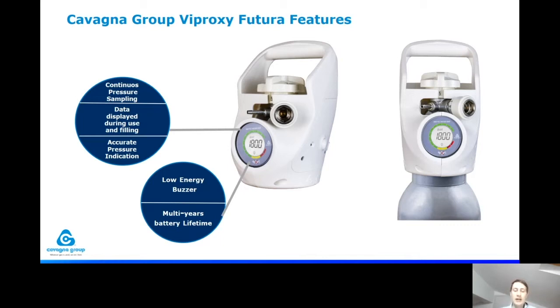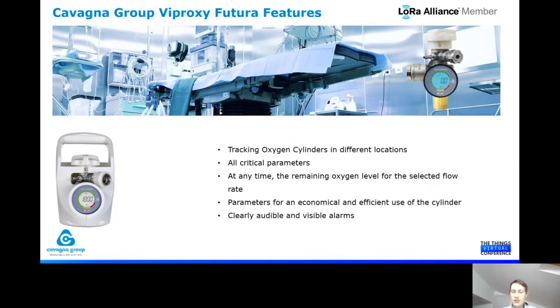This device, adding the LoRaWAN capabilities and communication, allows tracking of the oxygen cylinder in different locations, which is very important because this asset is crucial for the healthcare sector. We can monitor all the data the device collects, related to critical parameters of the patient, improving the service that nurses or doctors can offer. At any time, we can see the remaining oxygen level according to the selected flow, allowing a better and more efficient use of the cylinder.